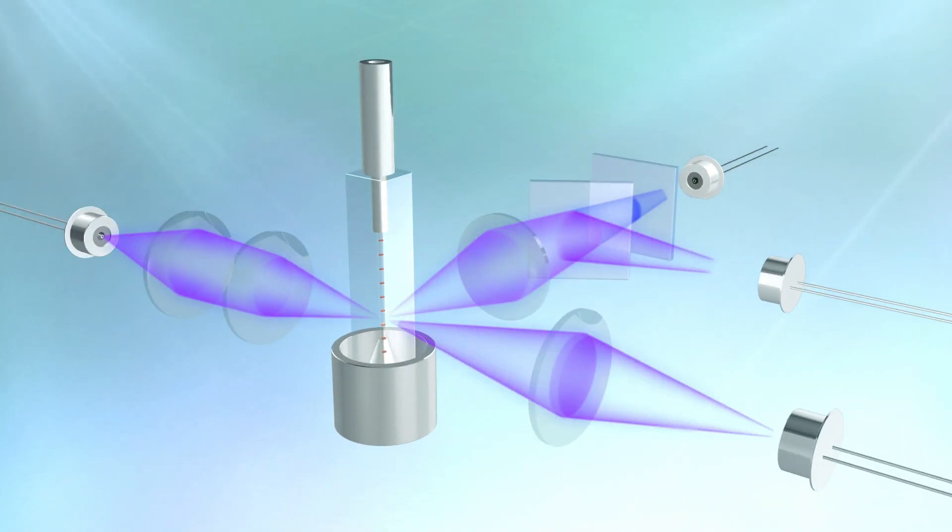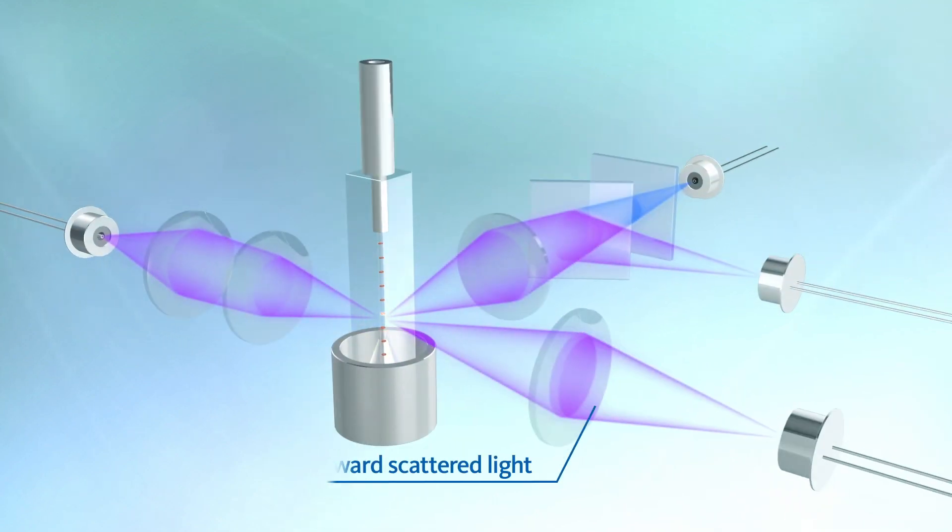The XN31 irradiates the cell with a 405 nanometer laser beam and counts the infected RBC by directly detecting the parasite's DNA, using forward-scattered light, side-scattered light, and side-fluorescence light.